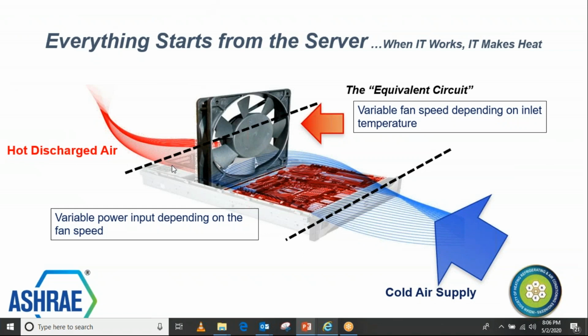Now, we will learn a little more about data center precision AC. This is just a typical example of a server, or a switch, which takes front supply and has rear discharge. This is the fan which is sucking the cold air. So it is very important, whatever technology you use. Imagine that someone says, I will install comfort AC, and I will install more capacity. No matter, obviously you can install it, no issue. But what will you achieve? You will end up consuming, as we discussed in the previous slide, so much power to deliver just the required sensible capacity, and you will have to replace those units so many times, given the short life span of those units.